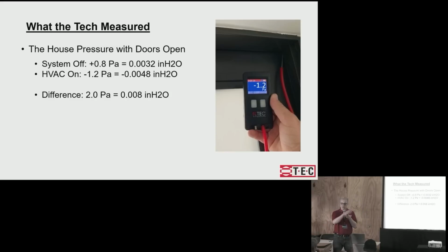Okay, so this is what I mean by house depressurization test. This is different from a blower door. You're not using the blower door to pressurize the house. You're actually using the HVAC equipment to see if the house pressure changes. The system-off pressure shouldn't necessarily be zero. That's just because of the stack effect. The temperature difference between indoors and outdoors will create a pressure that's not zero.